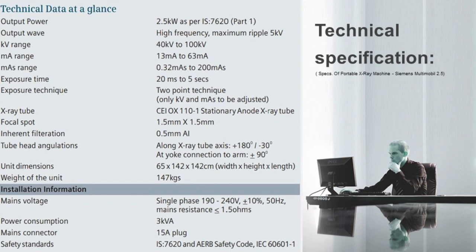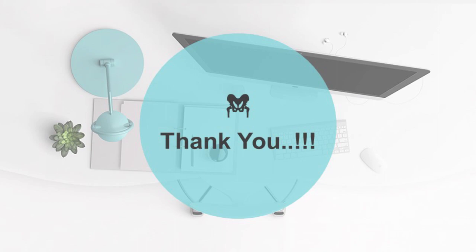Let's look at the technical specifications of a portable X-ray machine, the Siemens Multimobil 2.5. It has an output power of 2.5 kW, an output wave of high frequency and a maximum ripple of 5 kV. The kV range is from 40 kV to 100 kV and the mA range is from 13 mA to 63 mA. The exposure time is from 20 ms to 5 seconds using a 2-point exposure technique. The focal spot is 1.5 mm x 1.5 mm, basic unit dimensions are 65 x 142 x 142 cm, and the total unit weight is 147 kg. So, though X-rays are not 100% safe, they are very useful for diagnosis if used in a safe and controlled environment.